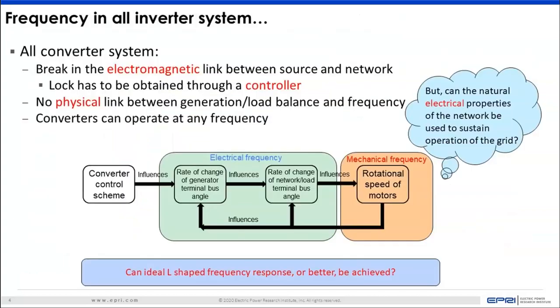Now, when you translate that to an all-converter system, immediately one has to realize that there is a break in the electromagnetic link between the source and the network, and instead that lock has to be obtained using a controller. And there's no physical link between generation-load balance and frequency. Of course, if one puts in a load event, one would see the frequency dropping or the rate of change of angle changing in a manner which one might assume is like frequency as we know it from a conventional system, but there's actually no physical link from electromagnetic properties, and converters can operate at any frequency.